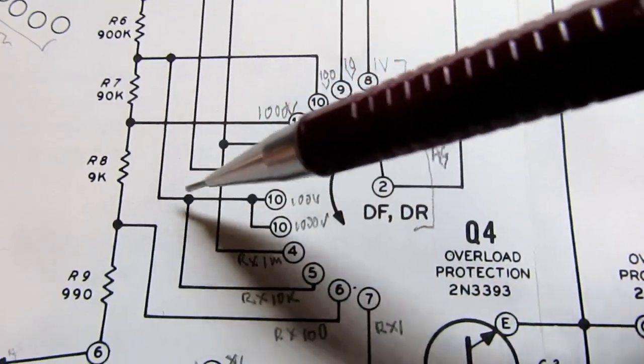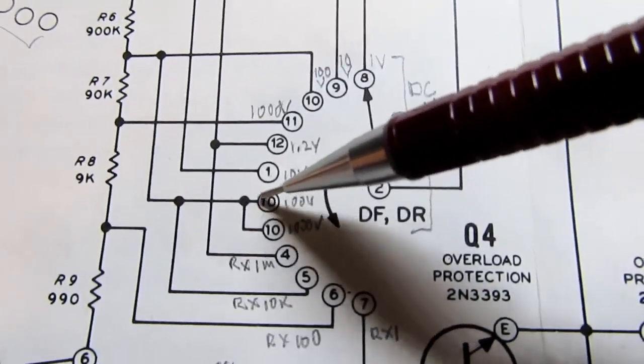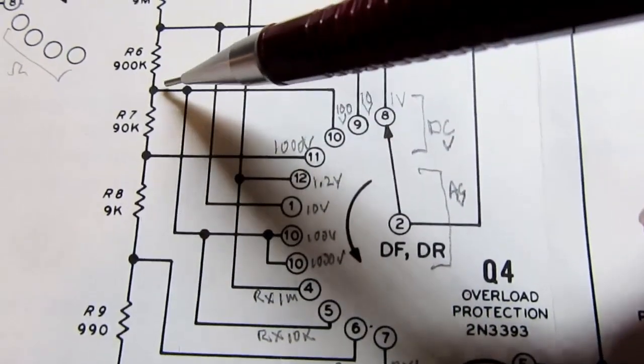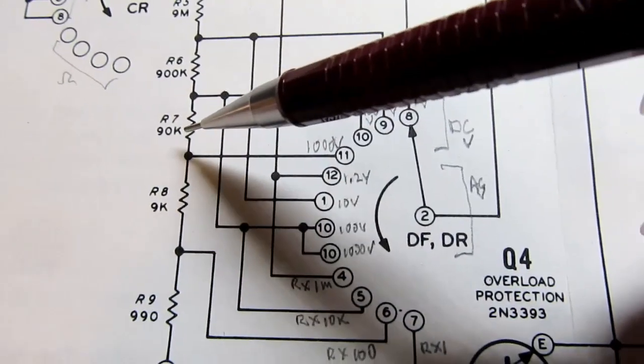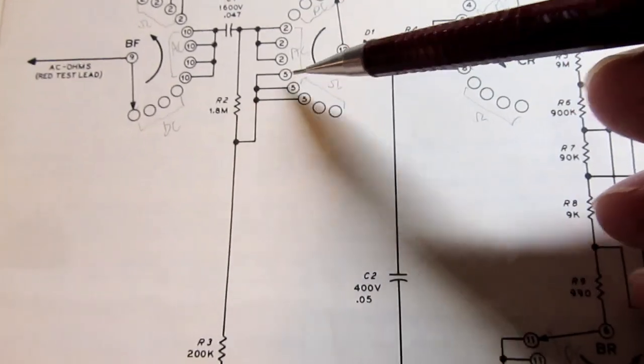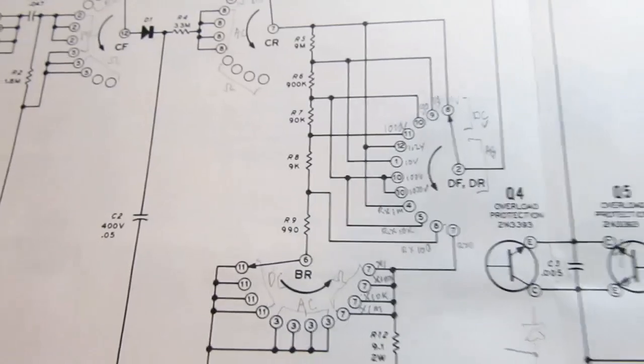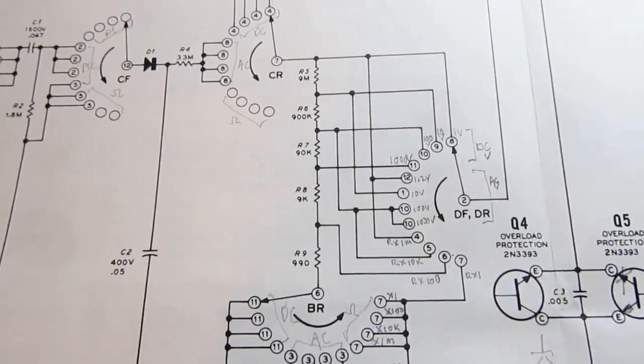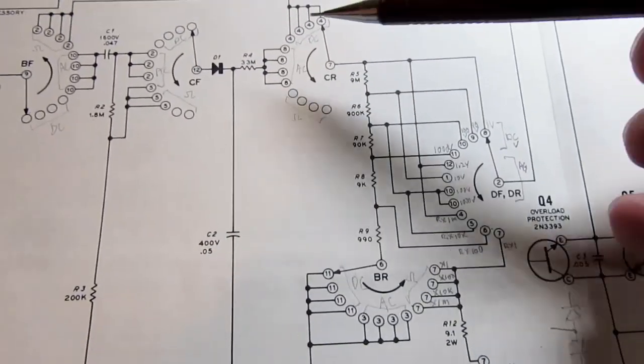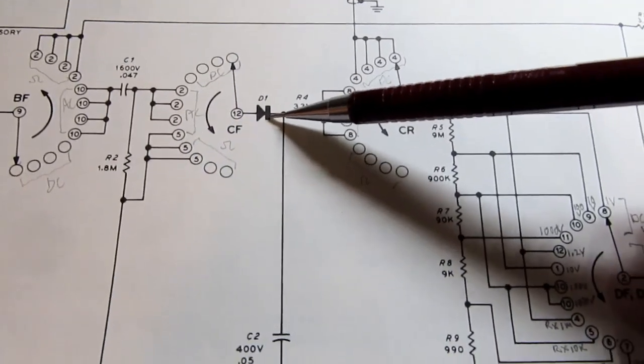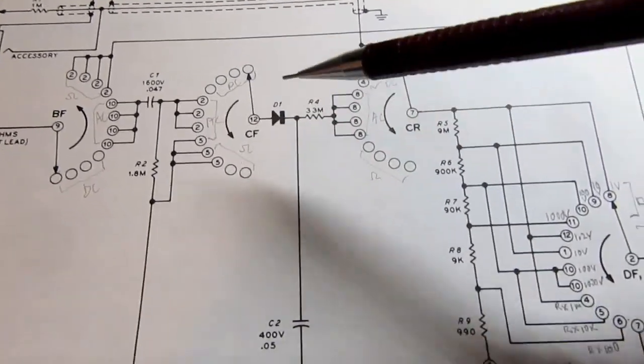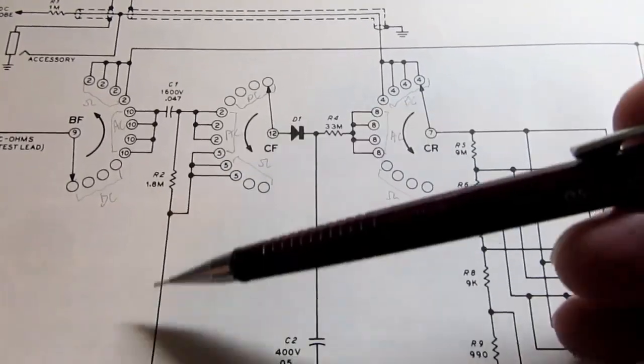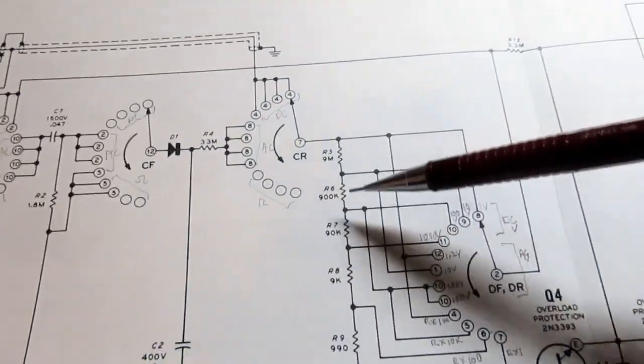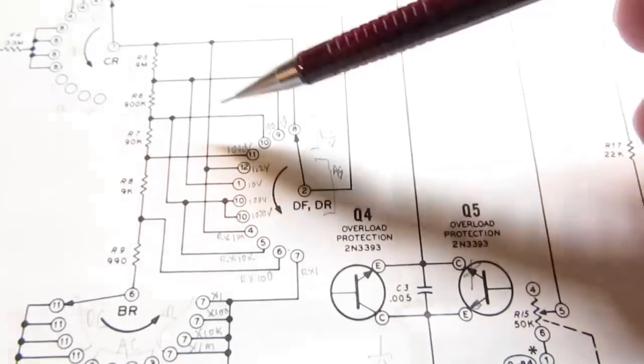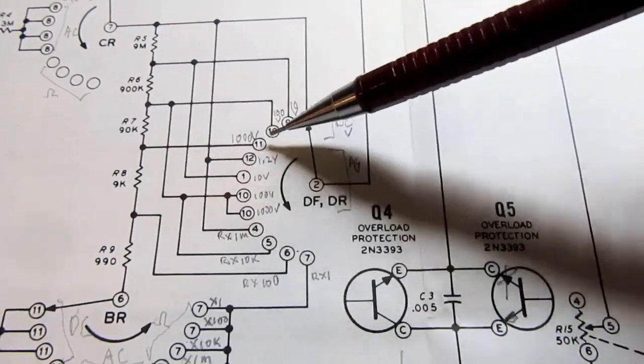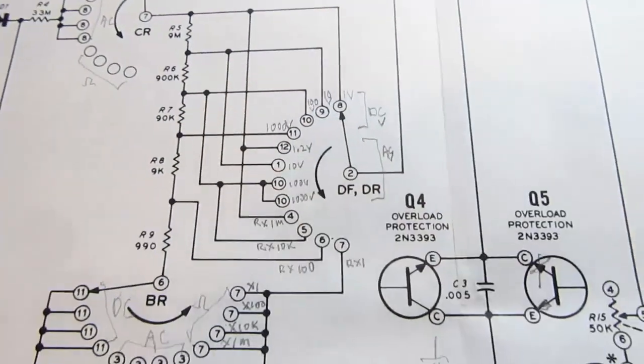1 point higher up. Yeah, so both 100 volts and 1000 volts are treated the same when you're dealing with AC volts, so that's tapping off the same point in this resistor divider, but that's compensated for by when you're in the 1000 volt range over here, you get some additional attenuation. And I think that's largely a trick that Heathkit's using to avoid having too much voltage applied to this diode. It's not rated for the highest voltage you can apply to this meter. So when you are in the 1000 volt range, it knocks it down before it's applied to the diode, then it gets rectified, then it's compensated for here, the fact that you had some attenuation here, it's compensated for by playing a game with the range switch and which part of the divider you're tapping off of here.